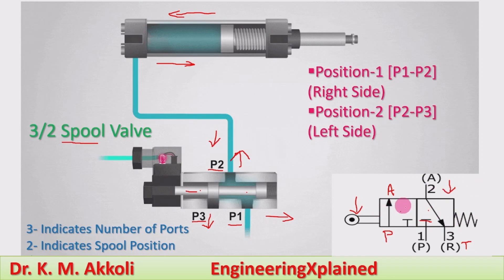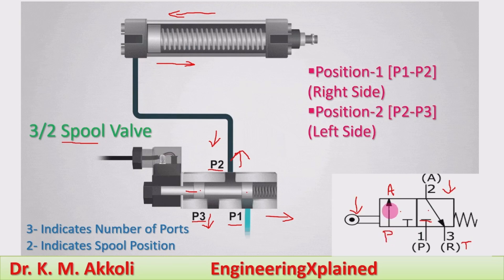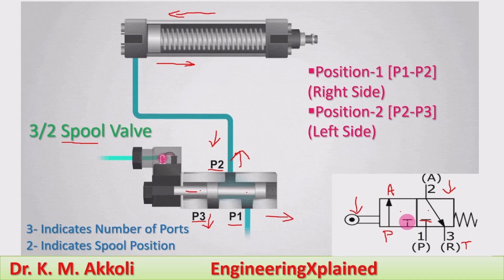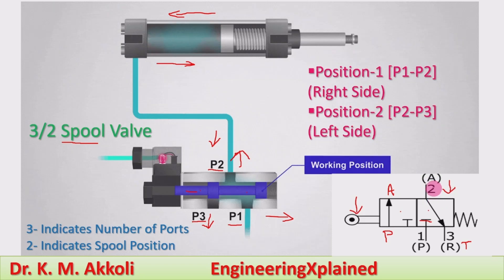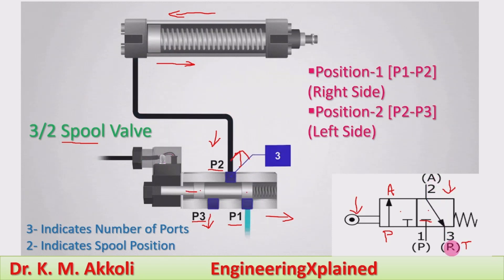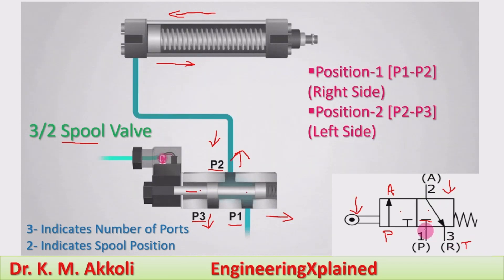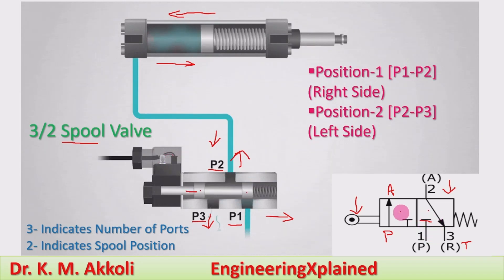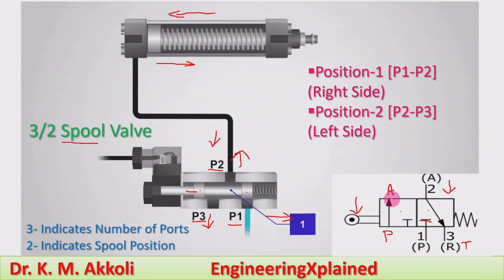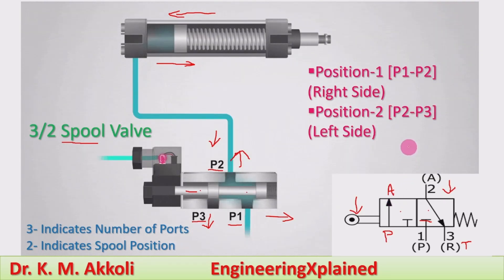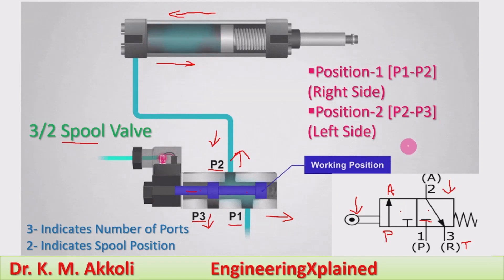In position one, the pump is connecting to the actuator and the return line will be closed. During the return stroke, the actuator line port connects to the return port towards the tank, and the pump port will be closed. Like this, the 3 by 2 spool valve operates. Similarly, the operation will be there for the other different types of spool valves, which I am going to explain in further sessions.